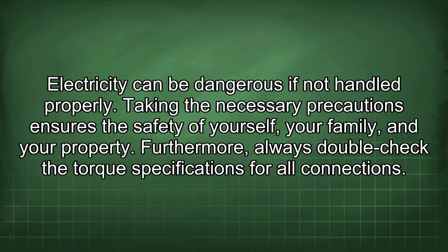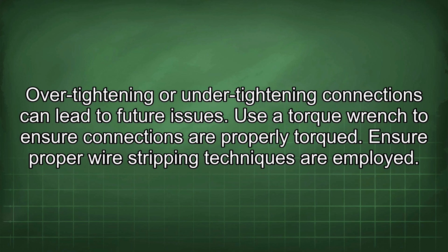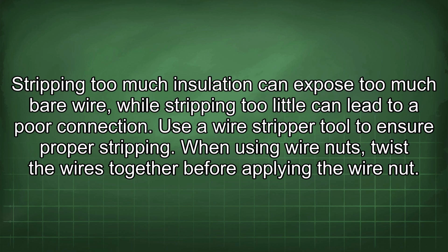Furthermore, always double-check the torque specifications for all connections. Over-tightening or under-tightening connections can lead to future issues. Use a torque wrench to ensure connections are properly torqued. Ensure proper wire stripping techniques are employed. Stripping too much insulation can expose too much bare wire, while stripping too little can lead to a poor connection. Use a wire stripper tool to ensure proper stripping.